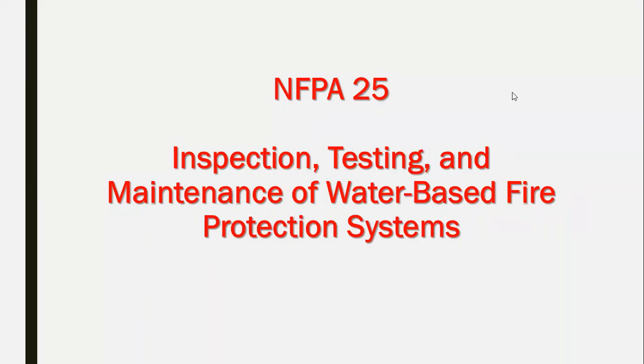Okay. Right. Let us start with this one, which will talk about NFPA section 25, the inspection, testing, and maintenance for the water-based firefighting system. It collects the testing and inspection which we applied before for all individual sections. So this NFPA 25 section will talk about the system as a system integration: the required test and inspection, weekly, monthly, and annually, applicable for all elements within the firefighting wet system.